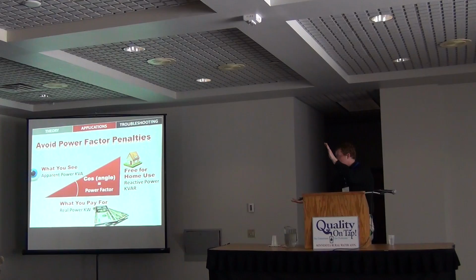And so the thought is, what we want to do is get this kVA line on top of that kW line, which basically means we don't have any reactive power. Using a VFD is a great way to do that, because a motor is 0.7, so that angle is a little bit bigger. If we get that angle down to 0, then the cosine of 0 is 1, so 1.0 power factor. Using a VFD is a great way to improve your power factor in your plant if currently you're getting dinged on power factor charges, because a VFD has basically unity power factor.